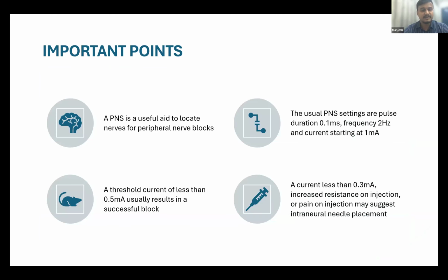Coming to the important points before concluding, a peripheral nerve stimulator is a useful aid to locate nerves for peripheral nerve blocks. The usual peripheral nerve stimulator settings are a pulse duration of 0.1 millisecond with a frequency of 2 hertz. A threshold current of less than 0.5 milliampere usually results in a successful block. A current less than 0.3 with increased resistance on injection or pain on injection may suggest that the needle is intraneural.